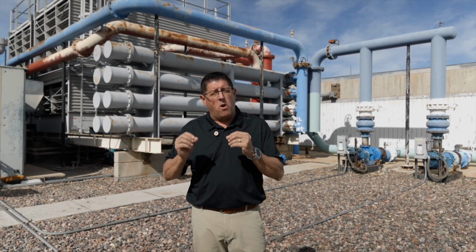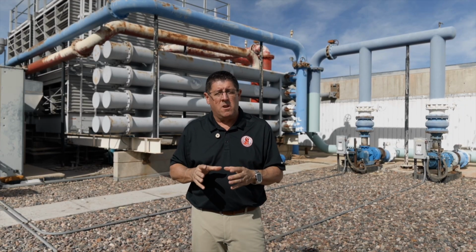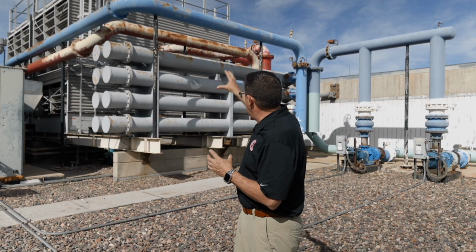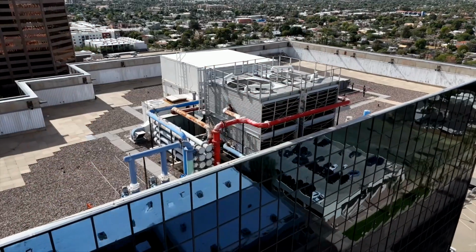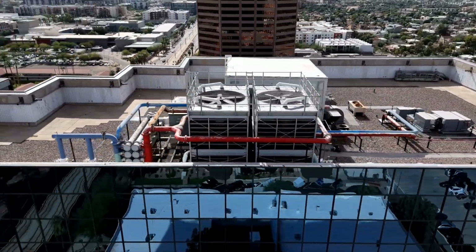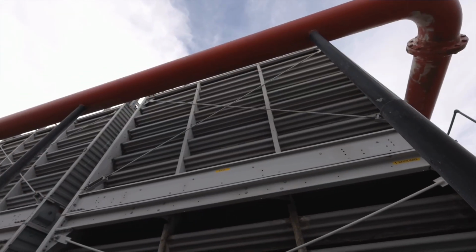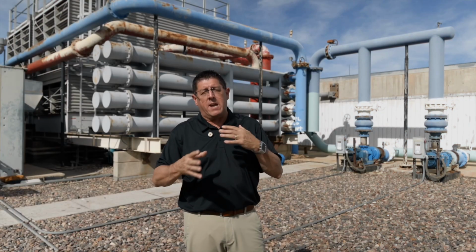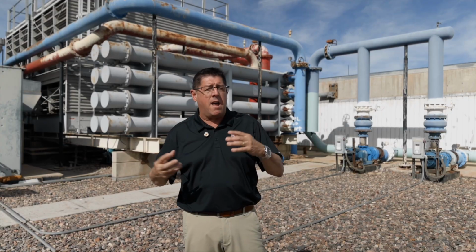Within this system, you're going to see a series of pipes. We have open loop pipes and closed loop pipes. The open loop we'll see is the red pipes behind us, and that's open to the atmosphere where we're expelling our heat from the system, and our closed loop, which is the tight system that is going in and out with the cool water. There's typically about a 10-degree difference between the supply and the return, or the open and the closed side. And that's all within the parameters on the inside of that cooling tower.